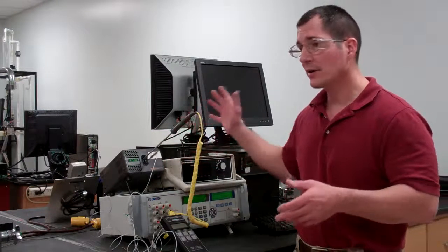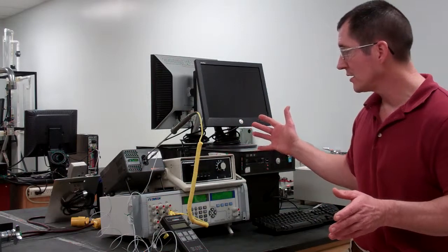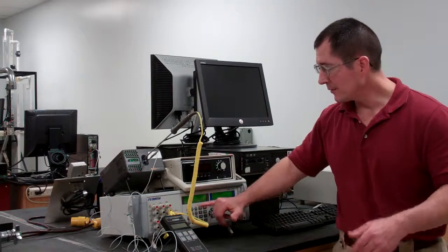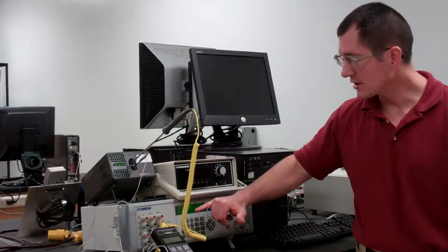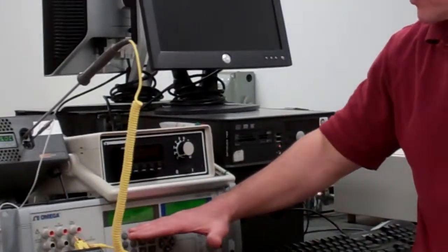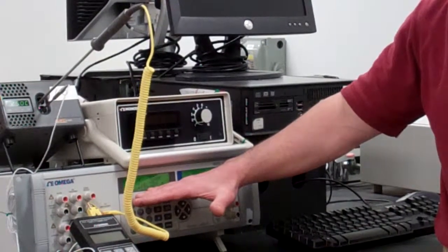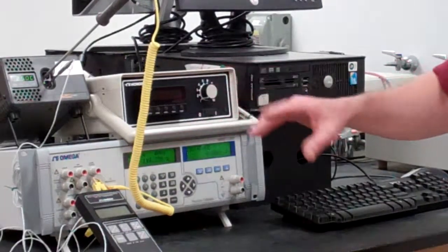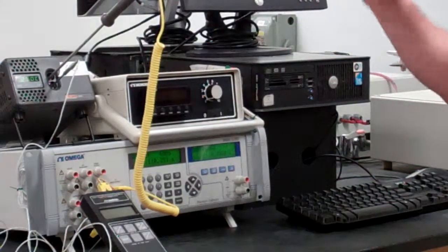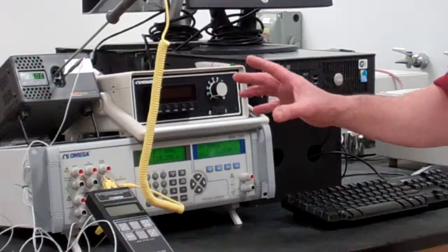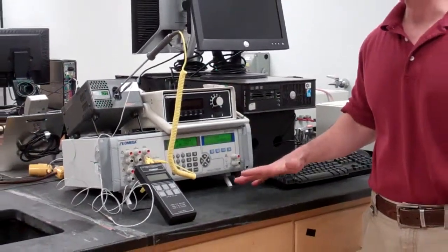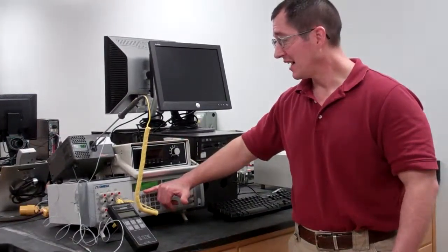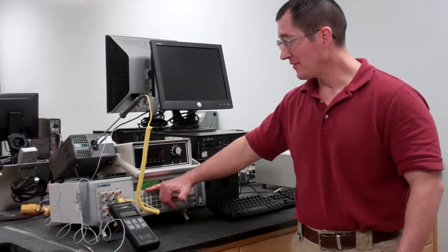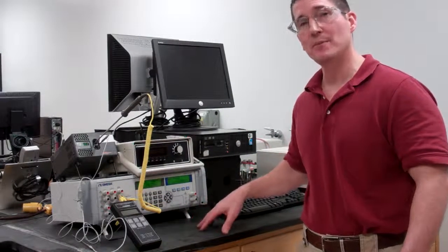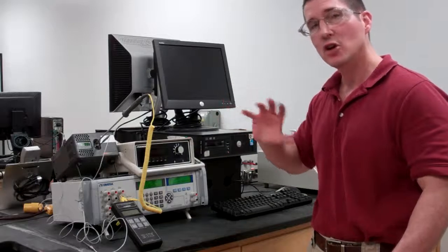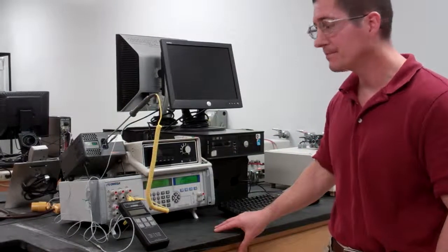It's been at 25 degrees for a long time now, so the signal should be relatively stable. If we look at the RTD input coming from this probe inside, it's giving me some resistance reading, and that's what the controller actually sees. Inside the controller is a table that tells it, if you're getting this signal, it translates into this temperature, so the controller can translate that information.